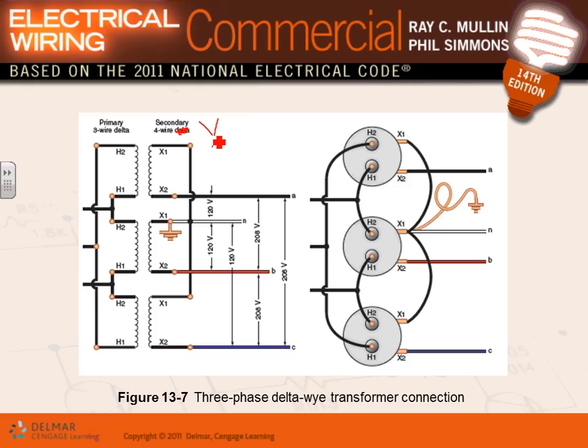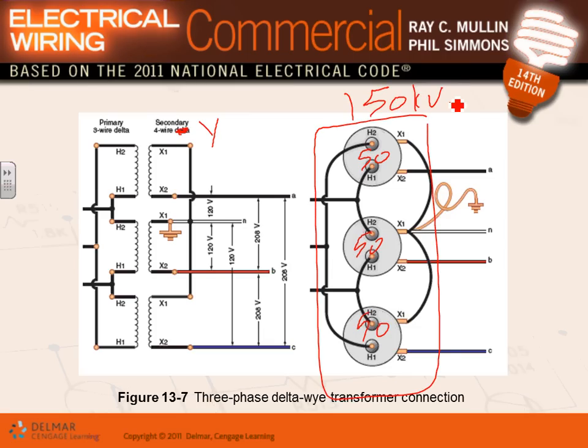That's the most common. Now, most of these are three-transformer banks. They call them banked together, guys, to get you a three-phase system. We did it in our lab. So if this was a 50 and this was a 50 and this was a 50, when you bank them together, this transformer bank is worth 150 kVA.